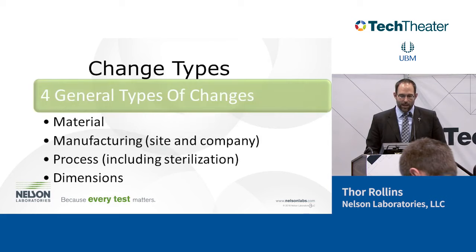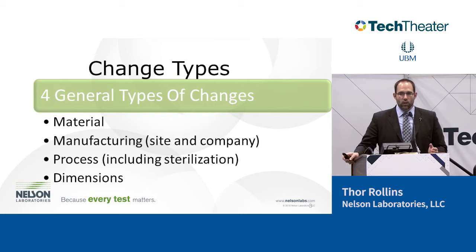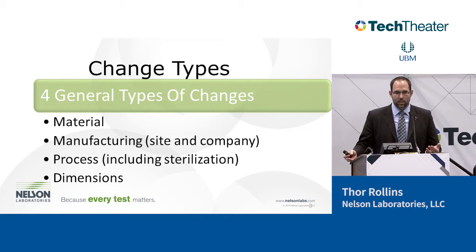I've seen four main types of changes with medical devices. The first, which we mostly see, is materials. Either a supplier runs out of a material and you have to switch to something they claim is the same, or you change suppliers, change locations, or actually change the material — going from a 304 to a 316 stainless steel, for example. What does that mean to the patient? Does it mean anything? Those are the kinds of questions we're going to try to answer today.